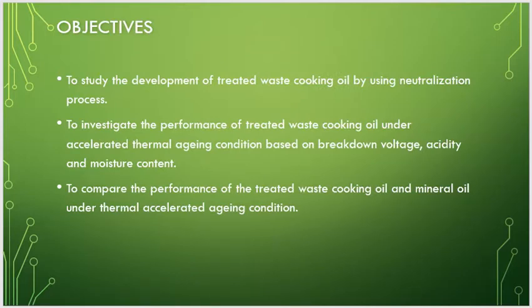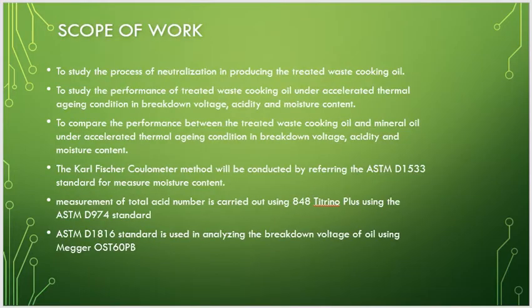The objectives are to study the development of treated waste cooking oil by using a neutralization process, to investigate the performance of treated waste cooking oil under accelerated thermal aging condition based on breakdown voltage, acidity, and moisture content, and to compare the performance of the treated waste cooking oil and mineral oil under thermal accelerated aging condition.